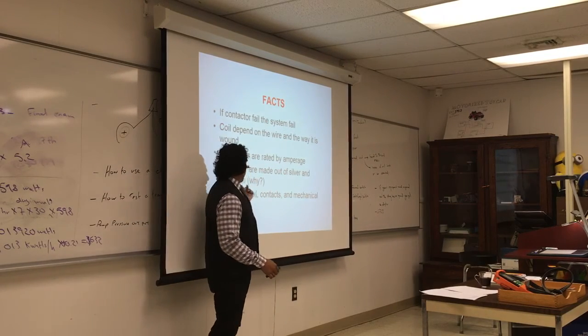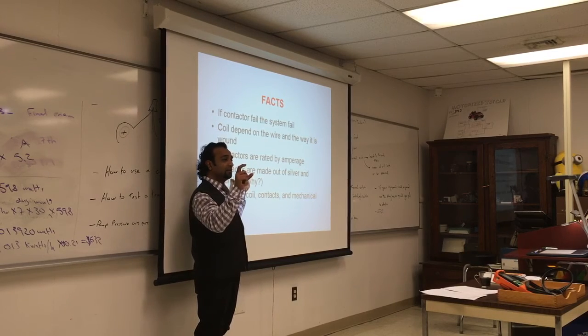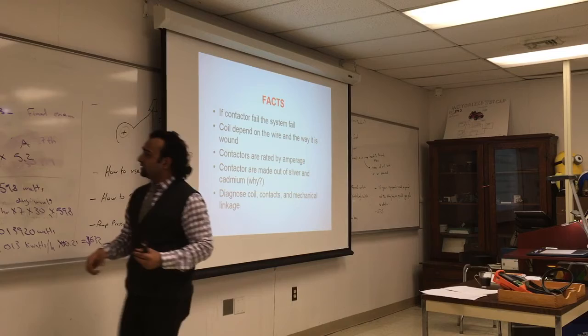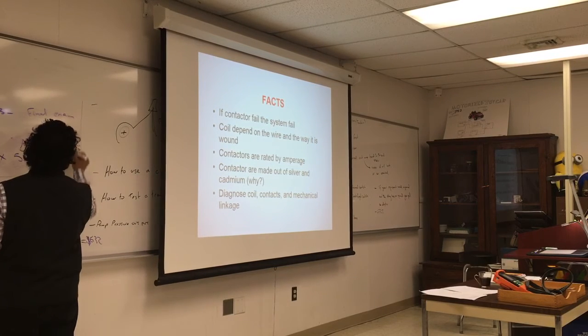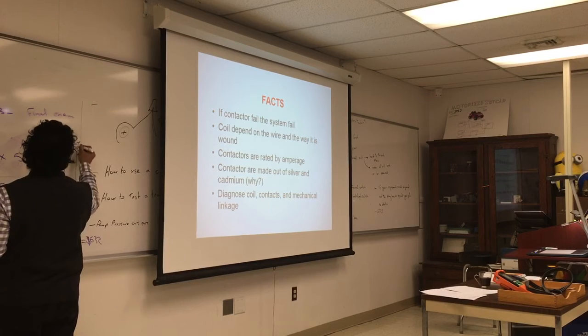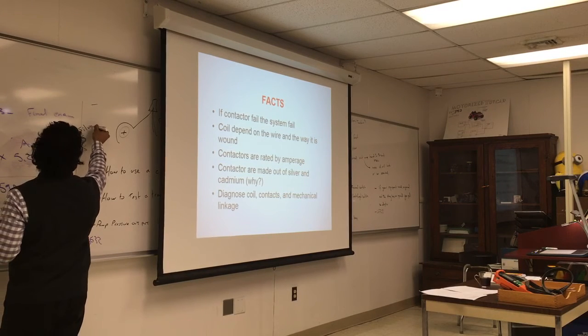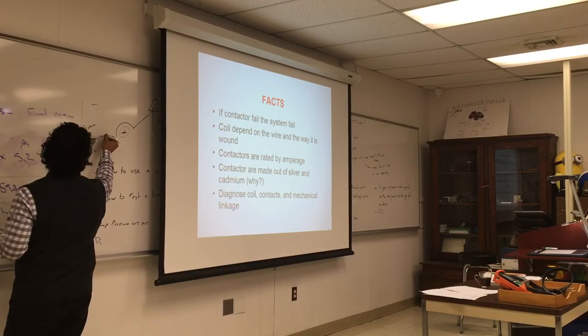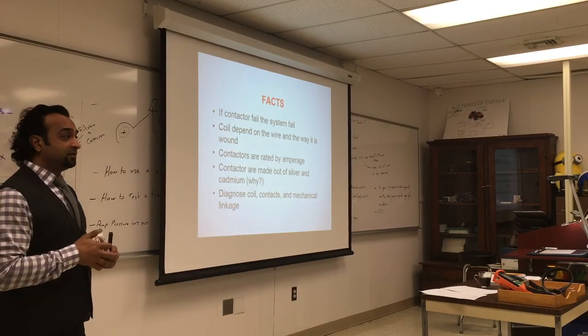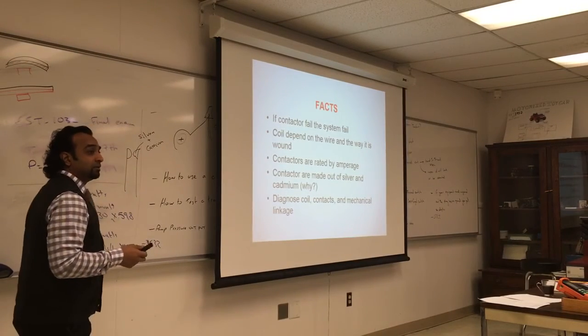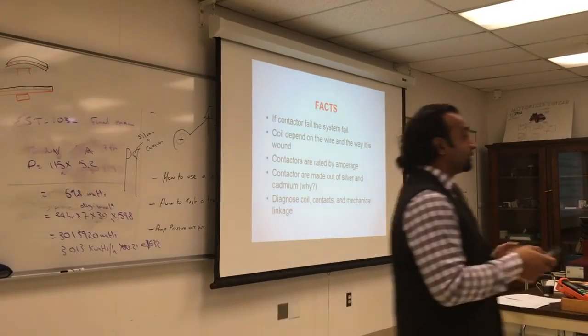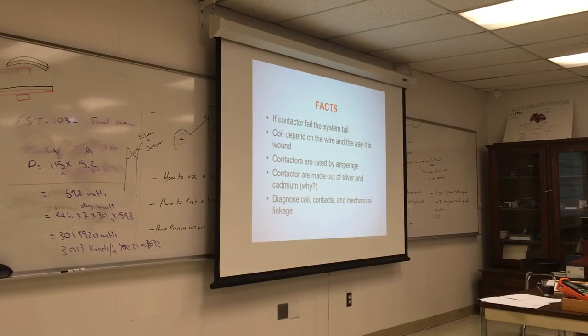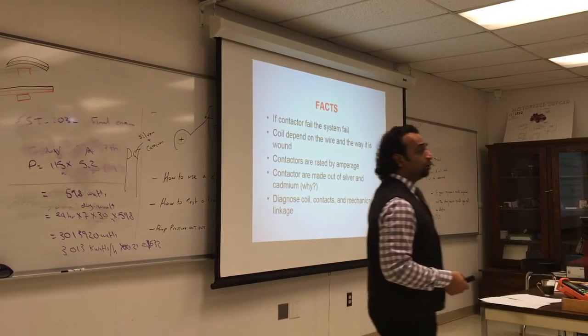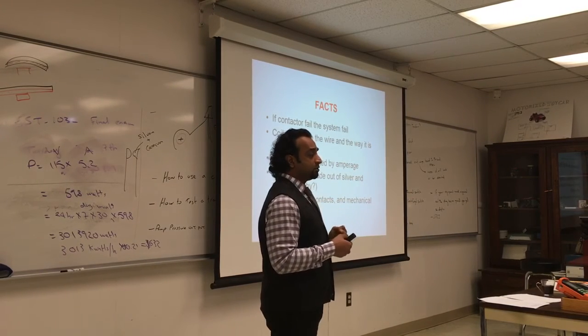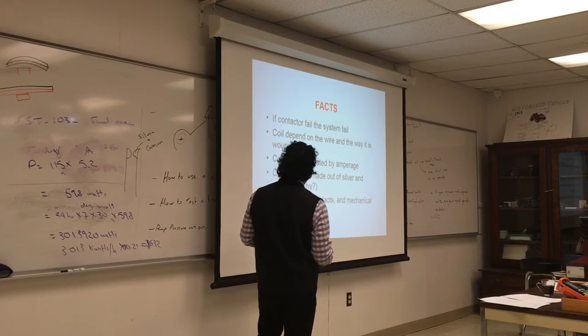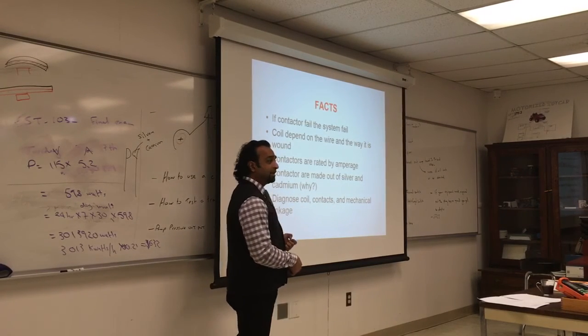Contacts are made out of silver and cadmium. That's the tip of the contactor, the little two pieces that join together. And why is that? So the tips have very good conductivity, and that's what makes them a little bit pricey. So those tips, they don't need much to connect. Once they touch, they will connect electricity. Best connectivity you can get. In some applications, they are gold plated because you don't want much force to have them conduct electricity. How to diagnose a coil? Contacts and mechanical linkage. We did that in the lab.